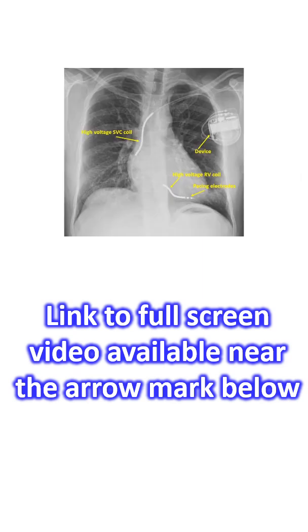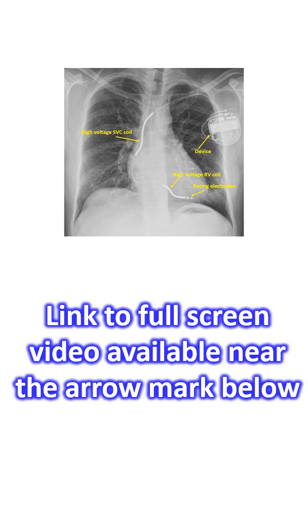These new types of ICDs have been innovated to avoid potential problems with transvenous leads in the conventional ICD system. Leads in the vascular system can get infected, can get fractured or dislodged, and occasionally perforate the cardiac chambers. Lead can also lead to intravascular thrombus formation. For these reasons, lead has been called the Achilles heel of most cardiac implantable electronic devices which include pacemakers and ICDs.